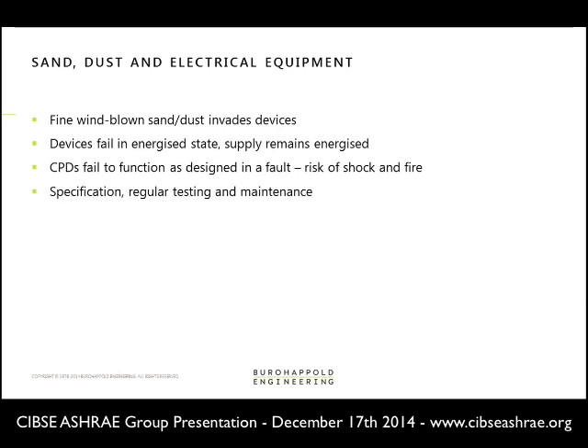Anti-condensation precautions have to be taken to ensure the continuous operation of electrical systems. There's huge problems with sand and dust and the electrical equipment. So the very, very fine wind-blown sand and dust invades devices. And what happens then is the devices fail in an energized state, but the supply remains energized. And then in a fault, CPDs can fail to function, and then there's a risk of shock and fire to building occupants. So to prevent this, you need to ensure correct specification and the regular testing and maintenance of installations and keeping installations dust-free.